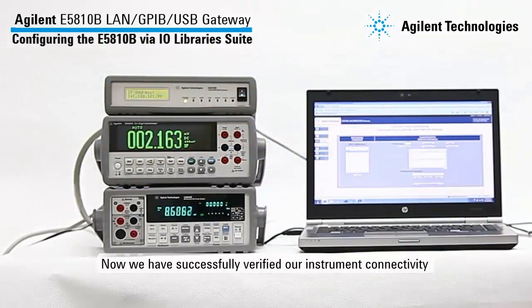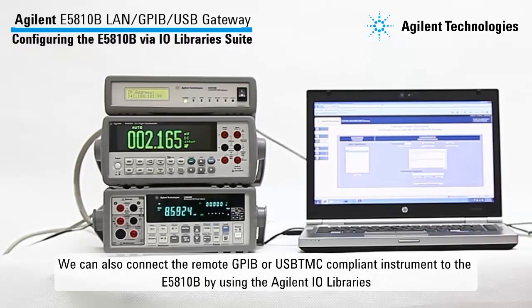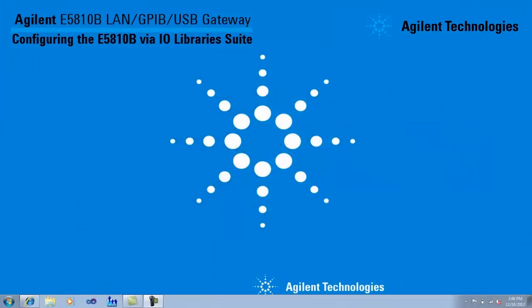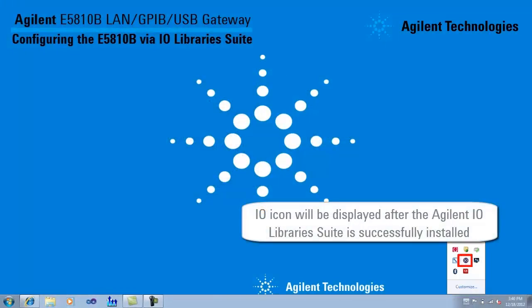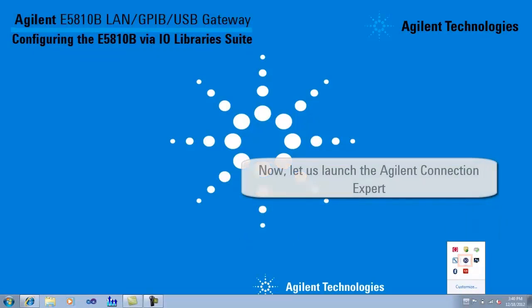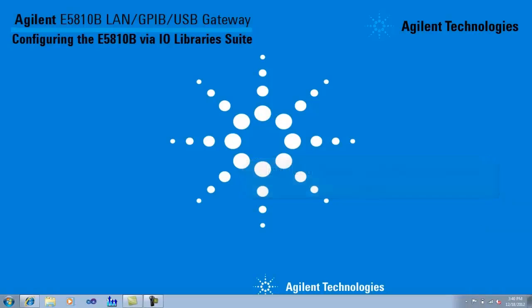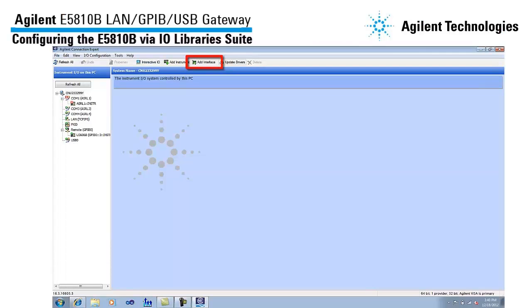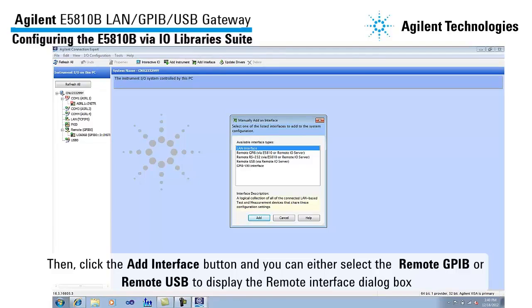Now we have successfully verified our instrument connection. We can also connect the Remote GPIB or USB TMC compliant instrument to the E5810B by using the Agilent IO libraries. You will see the IO icon on the Windows taskbar notification area after the IO library suite is successfully installed. Launch the Agilent Connection Expert from the Start menu or Start screen, then click the Add Interface button and select either Remote GPIB or Remote USB to display the Remote Interface dialog box.